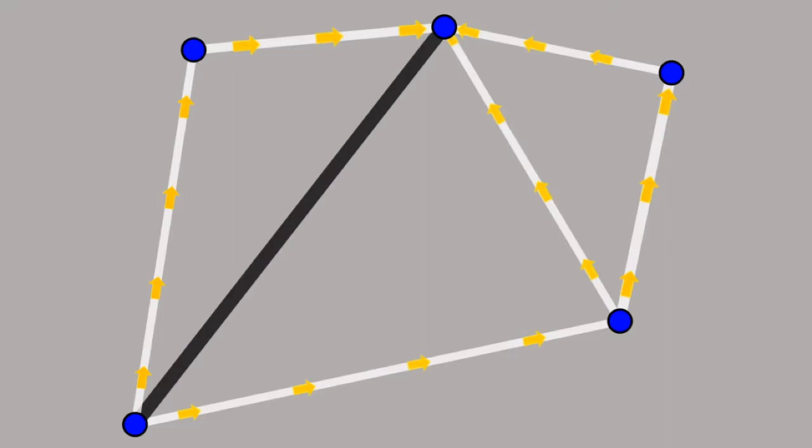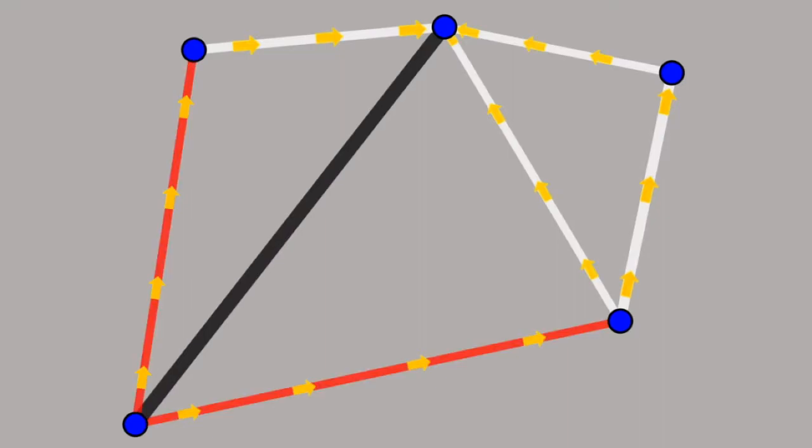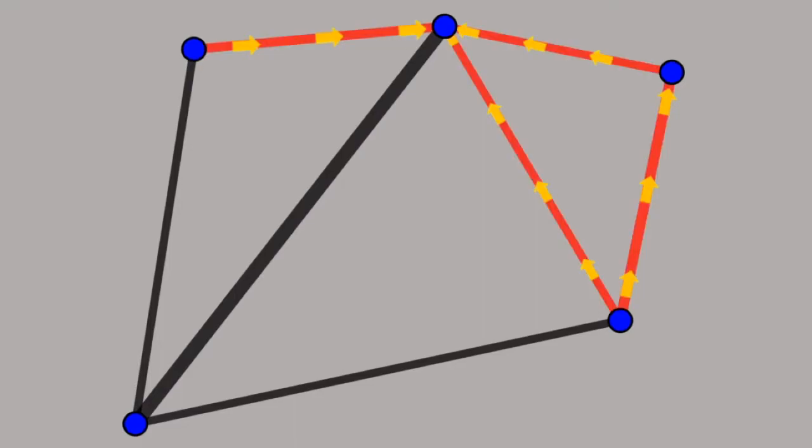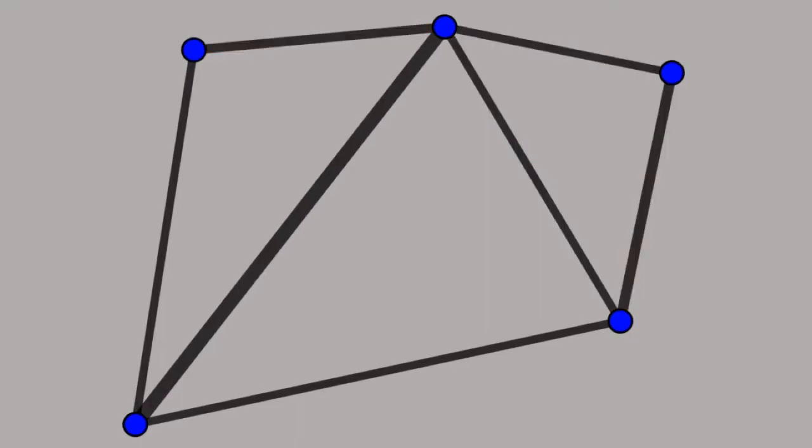The electrical energy which was transported by that line is distributed again to the other lines. Since these already transport as much electrical energy as they can with respect to the capacity, they are overloaded by the additional electrical energy and fail as well. This would give us a blackout again.